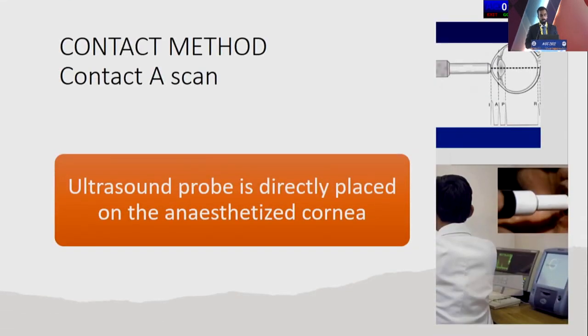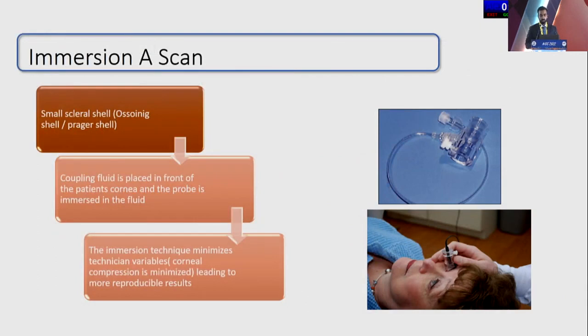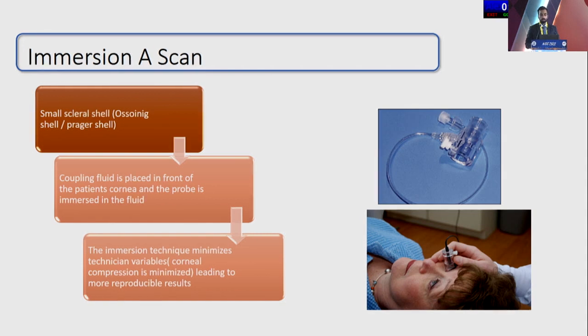The contact method uses the ultrasound probe, which is directly placed on the anesthetized cornea. This is the most commonly used method in most places, but it has the drawback of indenting the cornea, which will give you a fairly shorter reading than the true measurement of the axial length. Whereas in an immersion scan, we use the shell known as a scleral shell or a Prager shell. We use a coupling fluid in front of the cornea, and once the shell is placed on top of the cornea, it is filled with BSS. Then you can immerse the probe into the shell and get your reading. This negates the effect of the corneal compression and gives you a more accurate measurement of the axial length, leading to more reproducible results.